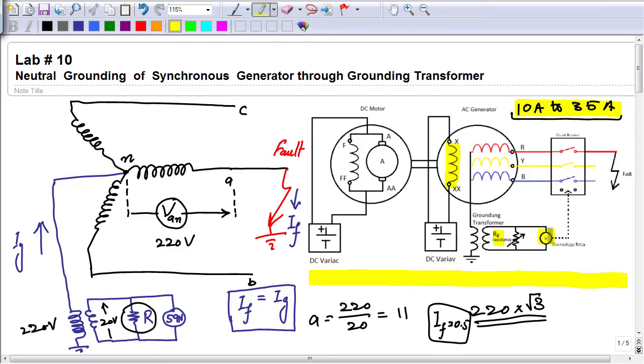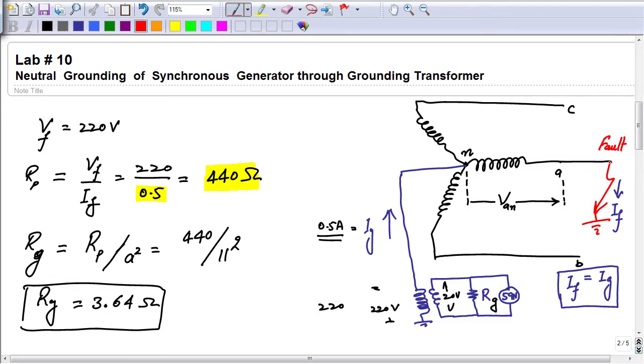Here we have used an overvoltage relay across this grounding resistance that we have inserted across the secondary of this grounding transformer. Now let's see how this will work. In case of a line to ground fault at the terminal of this winding, the full line to neutral voltage will appear across the primary of this grounding transformer, in this polarity plus minus. That voltage will be stepped down by this grounding transformer according to its transformation ratio. For example, in this particular condition, the primary is rated at 220, the secondary is 20 volt. So if a fault occurs here, 20 volt will appear across the secondary. If we set our relay to detect that voltage of 20 volt that would be here in case of fault, then we can detect the grounding of the fault, because in healthy condition no current will flow through this circuit, since we are assuming the system is perfectly balanced, or there will be very little leakage current.